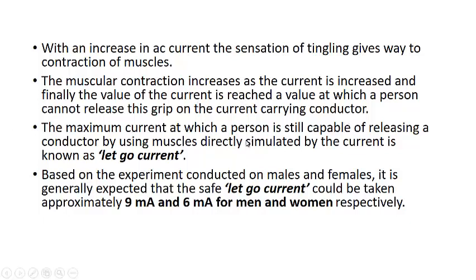The maximum current at which the person is still capable of releasing the conductor, that means he still has muscular control, is known as the let-go current. Based on experiments conducted on males and females, the safe let-go current can be taken approximately as 9 milliampere for males and 6 milliampere for females. With these values, we need to design the earthing, particularly in substations or sometimes in homes where we have to use an earthing system.